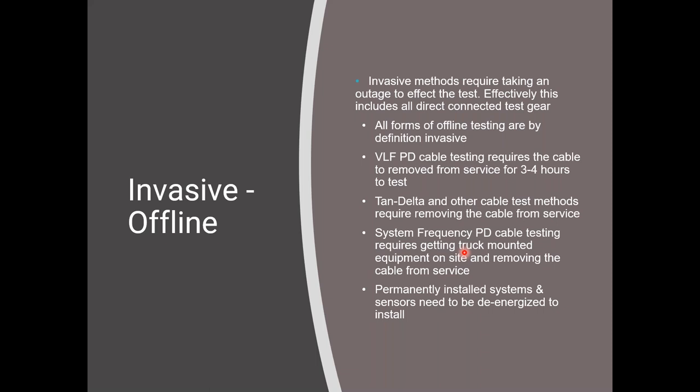Sometimes, based on the voltage level, so if you're testing a 265 kV cable, it may require equipment that's large enough that it has to be truck mounted. I've got an example of some smaller portable test sets that I think are good up to about 100,000 volts that are movable. It takes two guys to move them, but it's more portable than a truck-mounted system. So you have to know what your voltage ratings are going to be and what voltage class you're looking at to make sure you get the right test equipment for it.